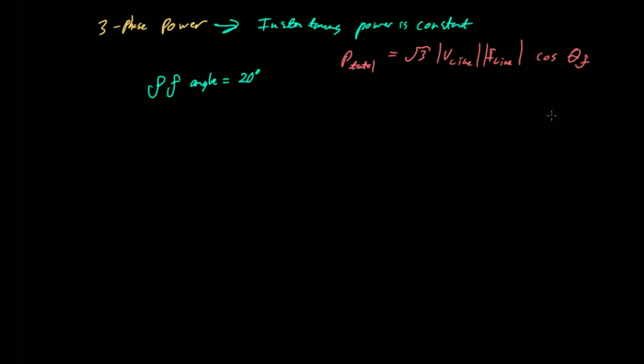So 60 hertz. We want to achieve a line voltage of 34.5 kilovolts, and we want the power factor to be 0.94. Those are our goals. However, when this manufacturing plant comes online, we discover that the power factor is 0.78. The plant tells us they need 24 megawatts. That's what we have to deliver to the plant. If we have to deliver 24 megawatts here, how much are we going to have to generate here? More than 24. And what causes our stock price to go down? The difference between this number and this number, which is presumably going to be burned up here. So we'd like to make this as efficient as possible, maximum power transfer.